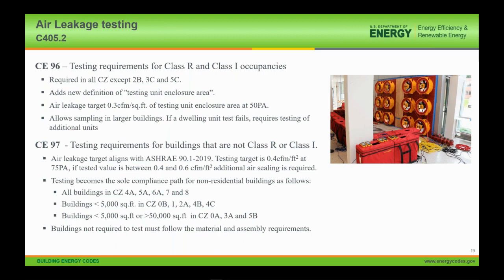A building with fewer than 8 dwelling units or sleeping units must test all the units, and larger buildings with more than 8 units will be allowed to use sampling. And that sampling will require a minimum testing of at least 7 units or 20% of the total number of units. And if any unit fails a test, projects will be required to test 2 more units. So those are the testing requirements for Class R and Class I occupancies.